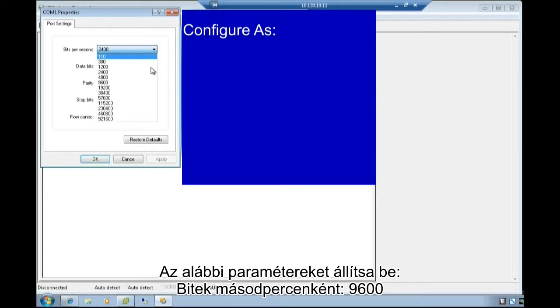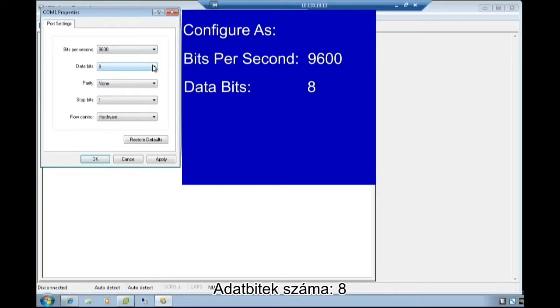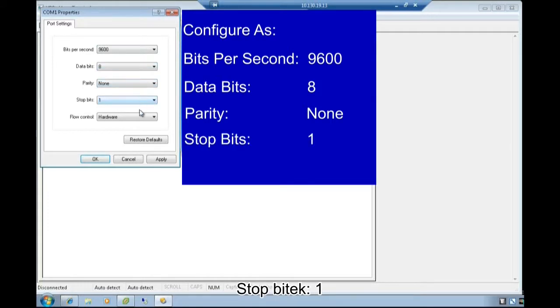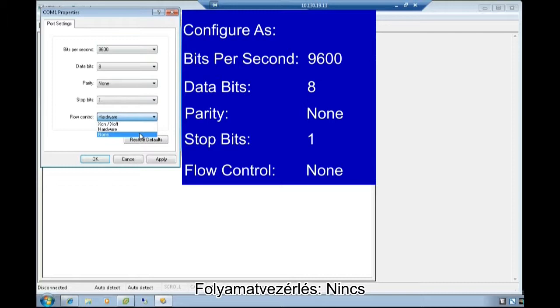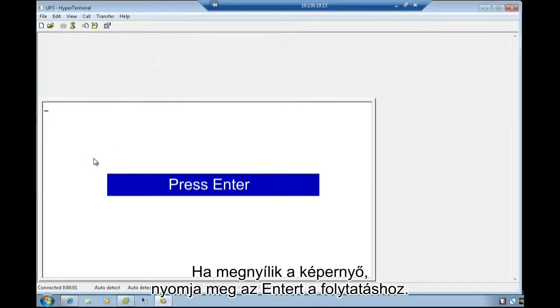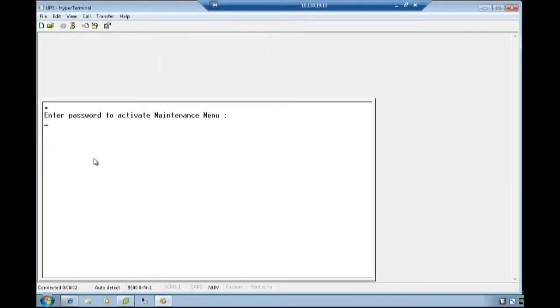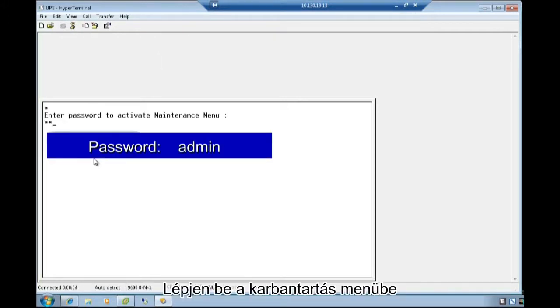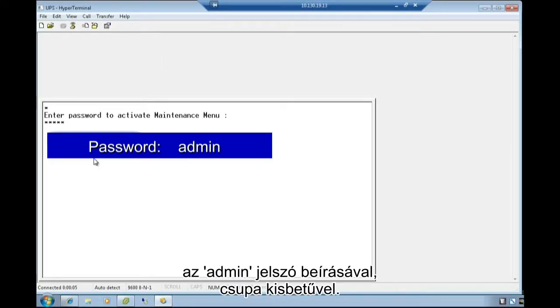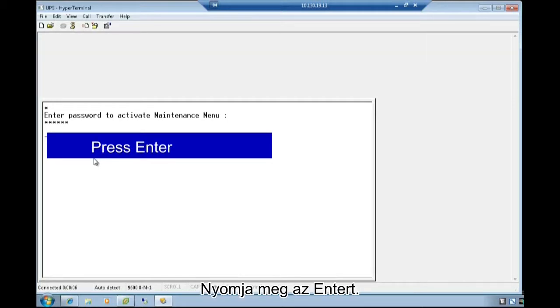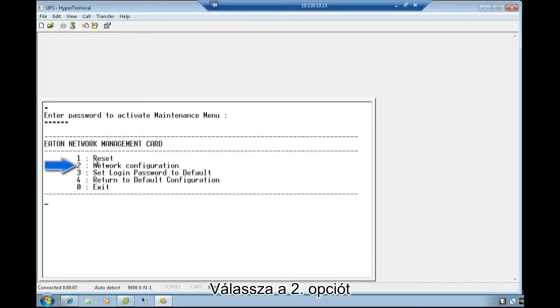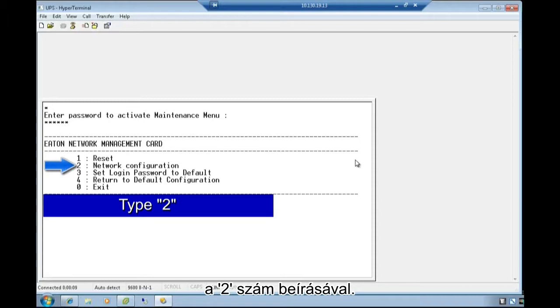Configure as bits per second 9600, data bits 8, parity none, stop bits 1. Flow control, none. Select OK. Once the screen opens, press Enter to proceed. Activate the maintenance menu by entering the password of admin in all lowercase. Press Enter. Choose option 2 for network configuration by typing the number 2.